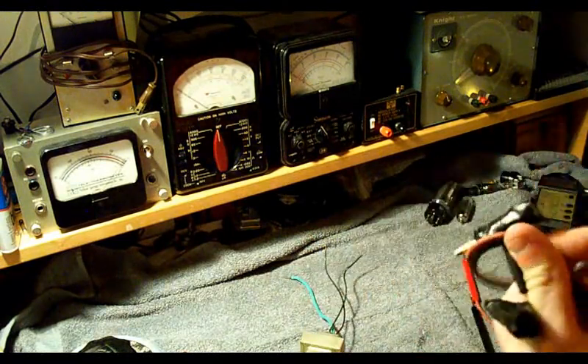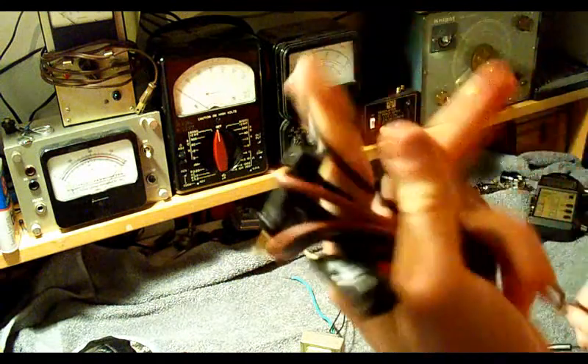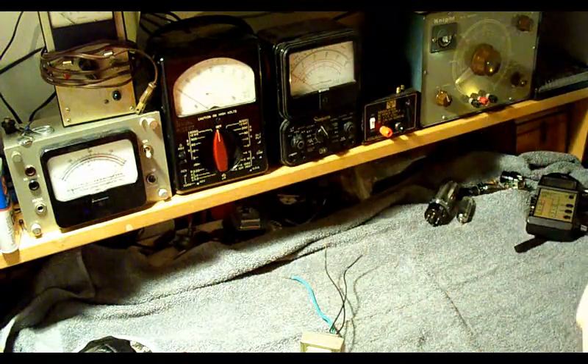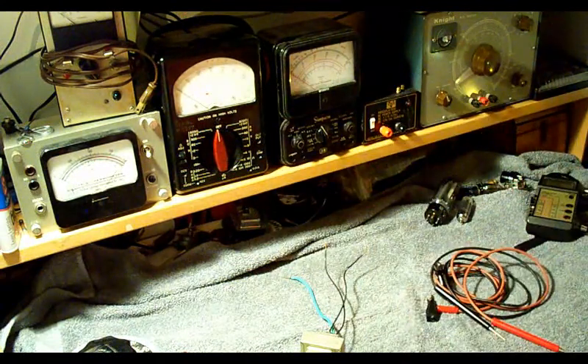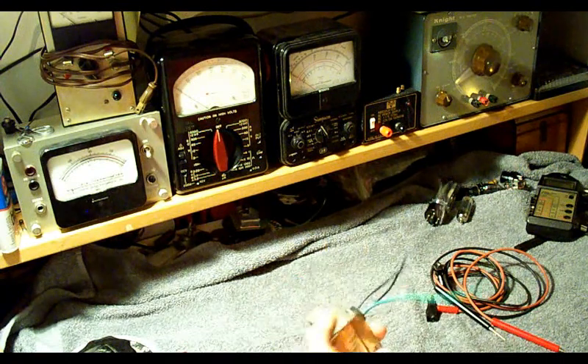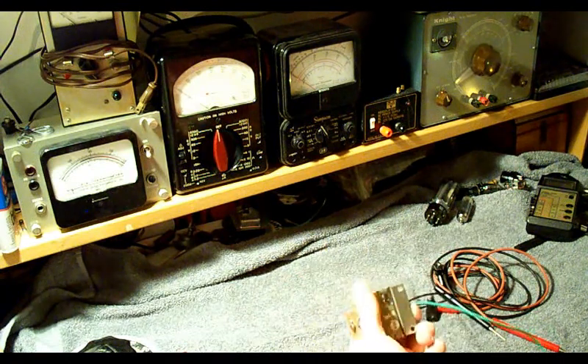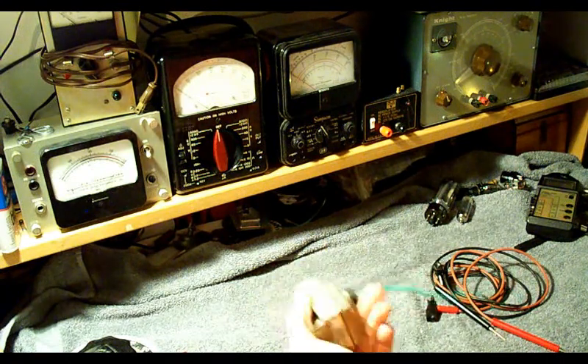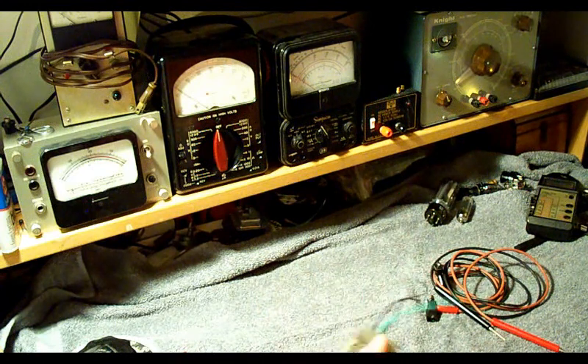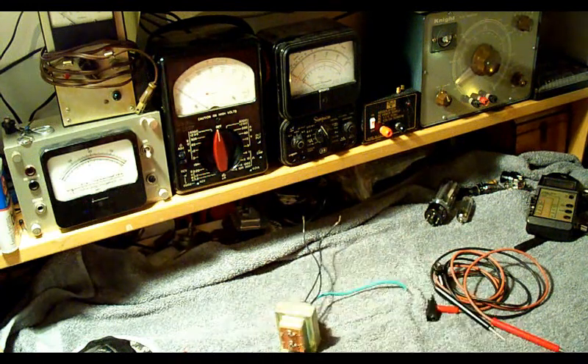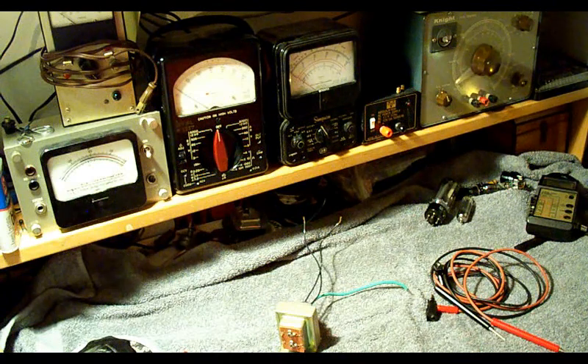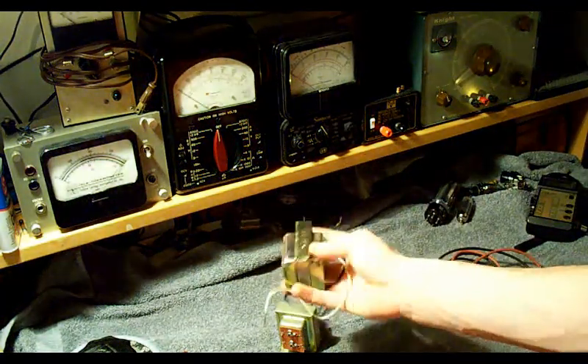Because you never know what can happen. This transformer must have been overheated or something happened to it clearly to cause that internal short. And I just so happen to be checking these transformers, and luckily I have spares, but this one is no good. And even if I got this repaired somehow, I would never trust it again. Clearly a transformer should never do that, as the windings are completely isolated.